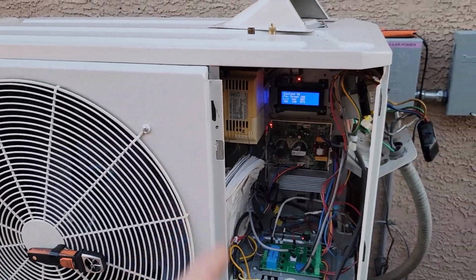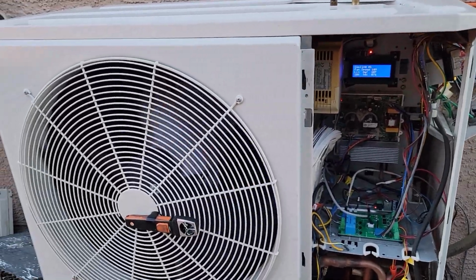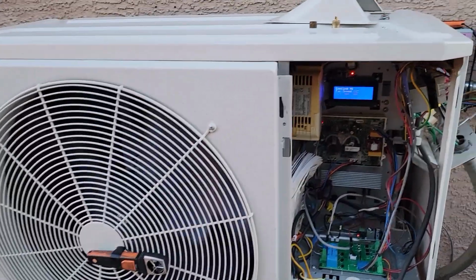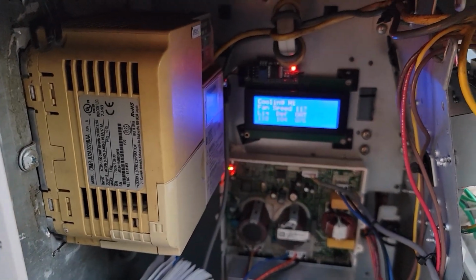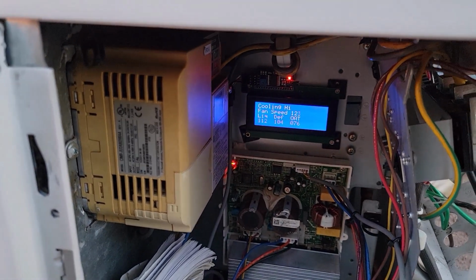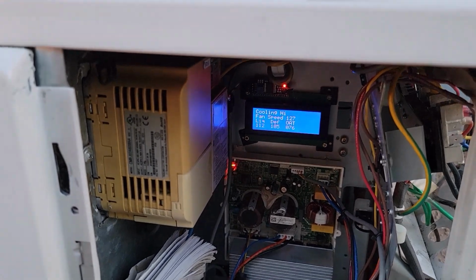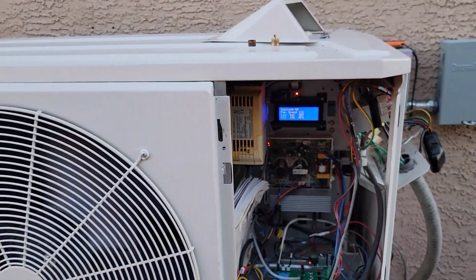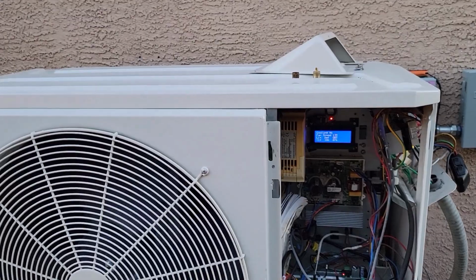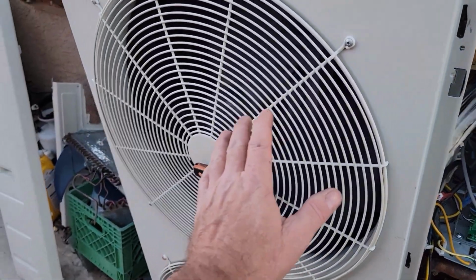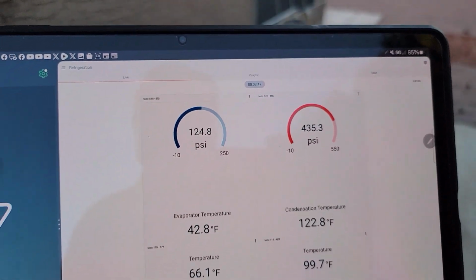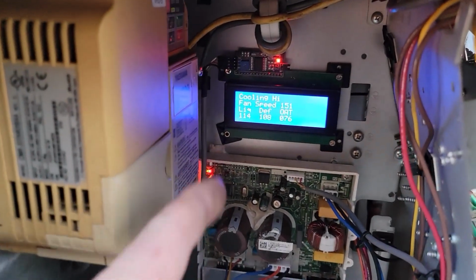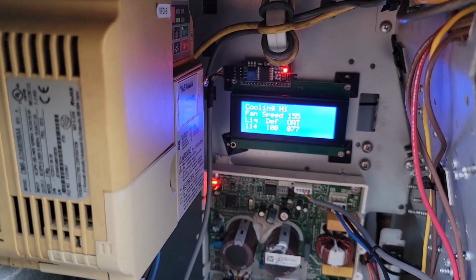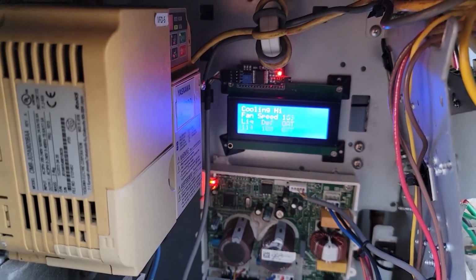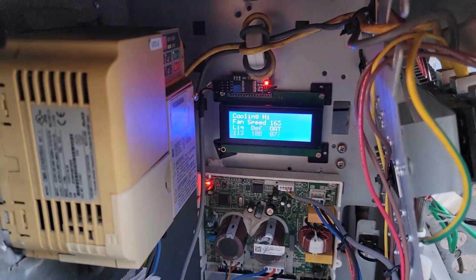I did tweak a little bit more with the program on that, so see if that catches it without having to jump to full speed. The liquid line gets up to, I forget what I put it to, like 117 or something like that. It just shoots up to full speed pulse width modulation. But I kind of doctored with that yesterday in my program. And you see the pressure's already dropping. Pressure's dropping, liquid line temperatures start dropping, and then it'll start backing off that pulse width modulation. So I might have to play with that a little bit to keep it from hunting or whatever.